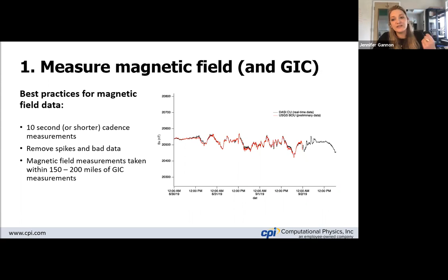So spikes, particularly from environmental noise, can be really important for transmission planning. And you want the magnetic field measurements to be as accurate as possible to your local area. There's not solid guidance on this, but multiple analyses are kind of converging on the idea that if you have the magnetic field within 150 or 200 miles of your GIC measurement, you can get most of the variation, although you won't get some of the high frequency information unless you're really close.